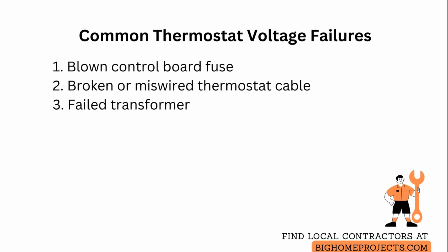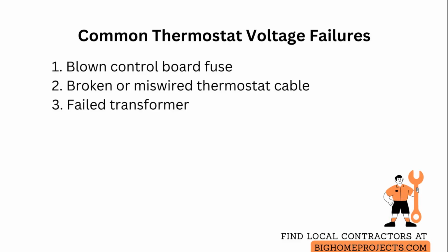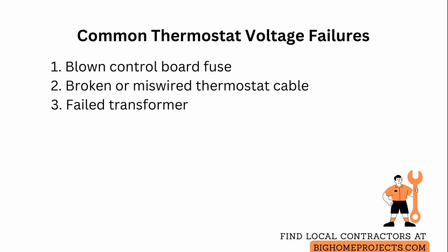For a broken or miswired cable, trace the conductors at both ends, re-terminate with proper ferrules or screw terminals, and use the same color convention to avoid miswiring during future service.